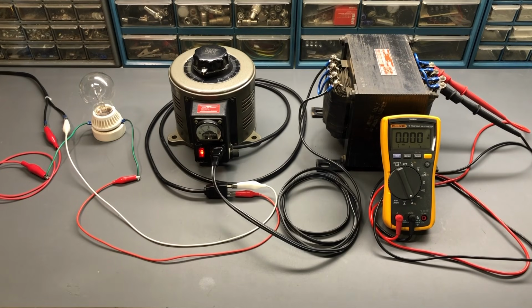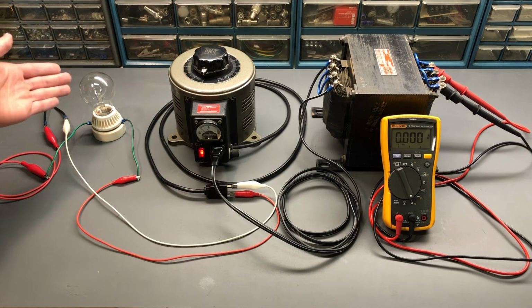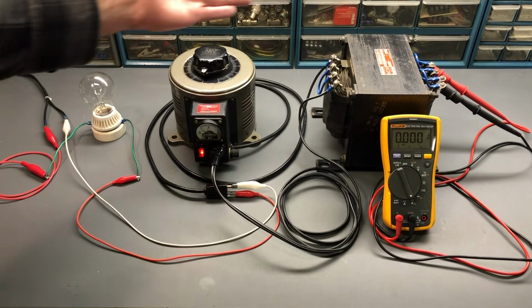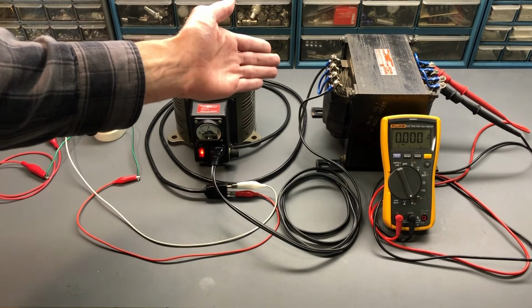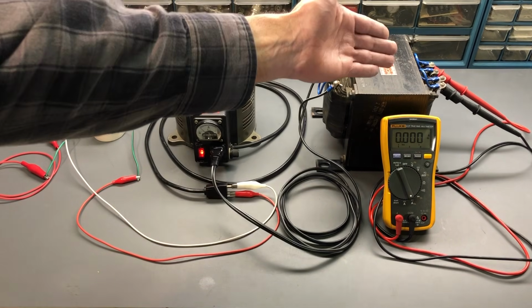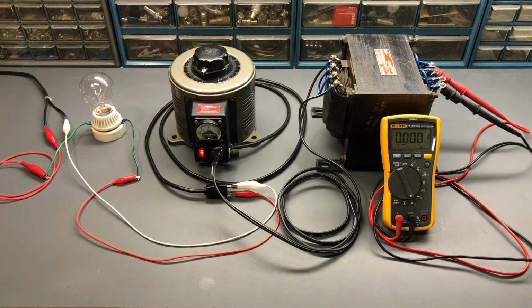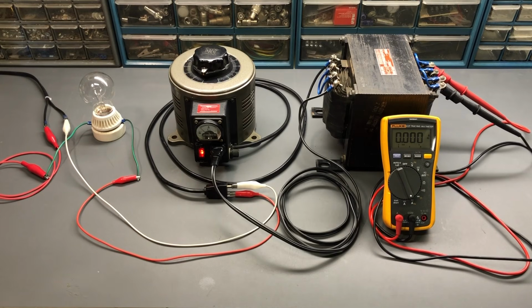A common question that comes up when you're designing an isolated dim bulb tester is, what order should the components be placed in? So should the incandescent bulb be electrically first, or should it be between the Variac and the isolation transformer, or what if it's placed on the secondary side of the isolation transformer? So we're going to find that out. I have 4 different circuits that we'll work through, 4 different configurations of these components, and we'll see exactly what effect it has when they're connected in different variations or different configurations.